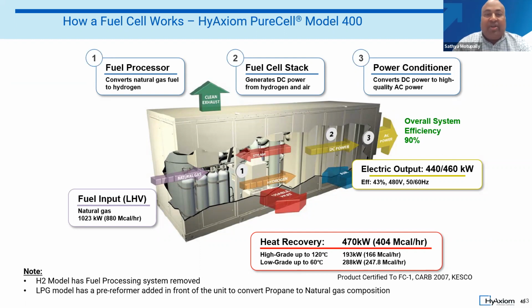The power generated in the fuel cell stack is taken to the power conditioner, which gives you very clean power. The power generated from this box is about 440 to 460 kilowatts, and the amount of heat generated is similarly about 450 to 470 kilowatts. So if you have a building that can use about 440 kilowatts of power and a similar amount of heat, this makes great sense, because it gives you very high utilization of the hydrocarbon fuel you're using to make power and heat on site.